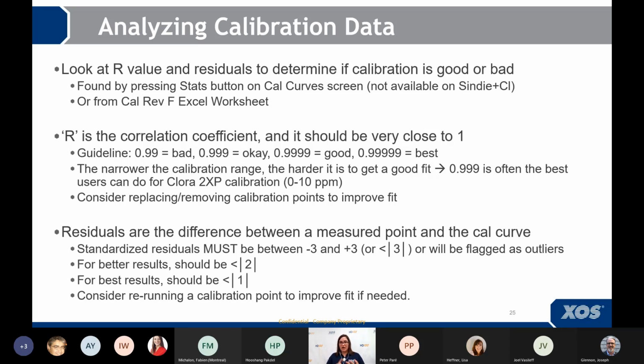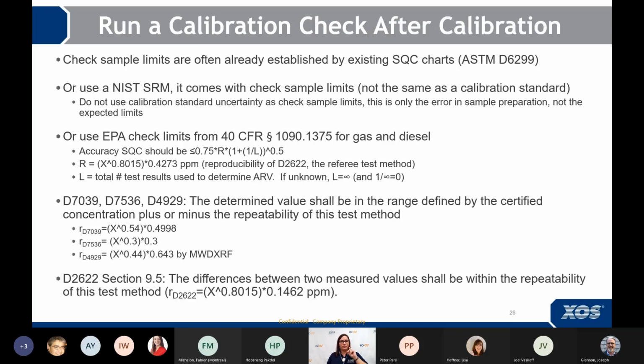So we put in our calibration and we're very satisfied with how it looks. So we're all done, right? Let's go celebrate. Wait a minute, one thing. Don't forget to run a calibration check. Okay, your calibration's not done until you've confirmed that your calibration is good.